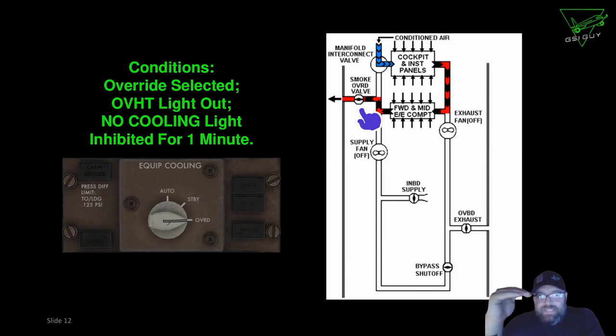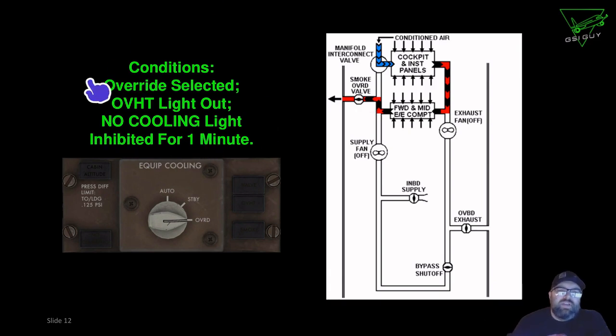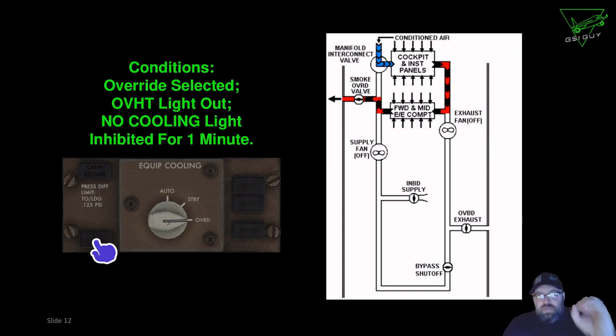And when it does that, that's when it knows that it's cooling at this point. All right, and that's where this is coming in over here. So, no cooling. Okay, so we talked about the overheat light at the standby position gets inhibited for 5 minutes. The no cooling light, which is located over here, is going to inhibit for 1 minute. That's all it inhibits, because that light tells me there is zero airflow going through the system.